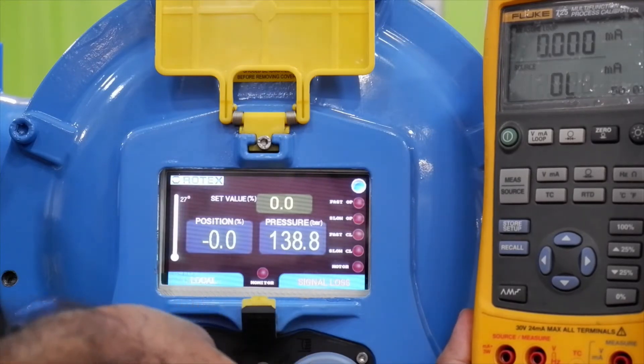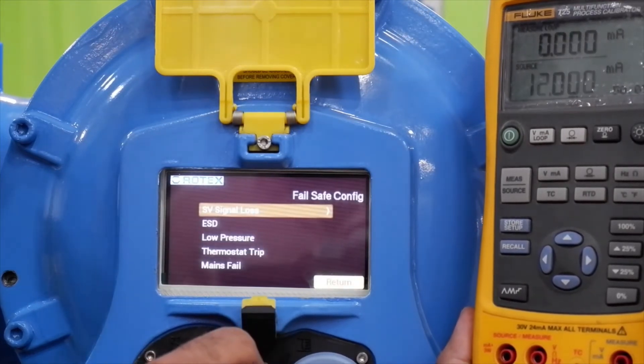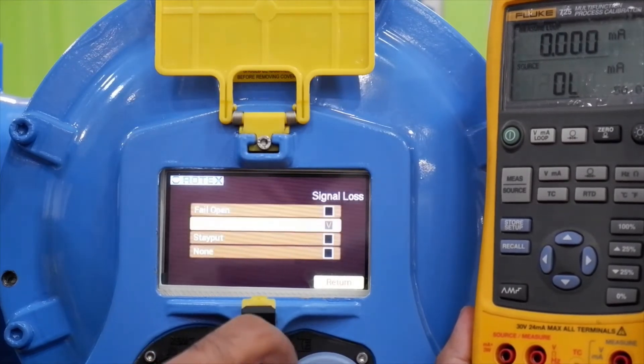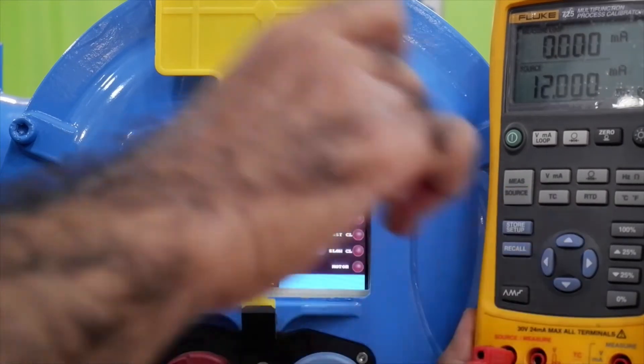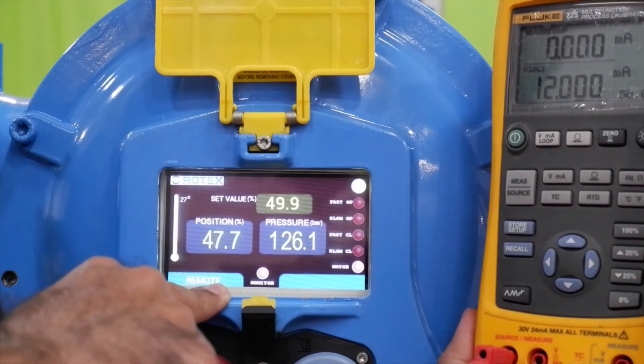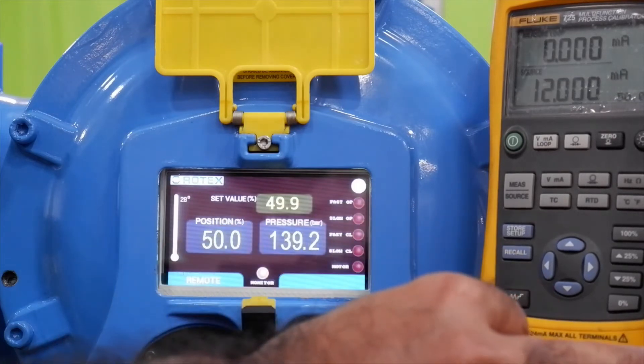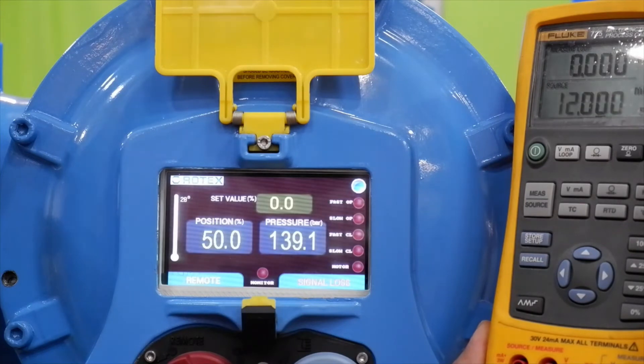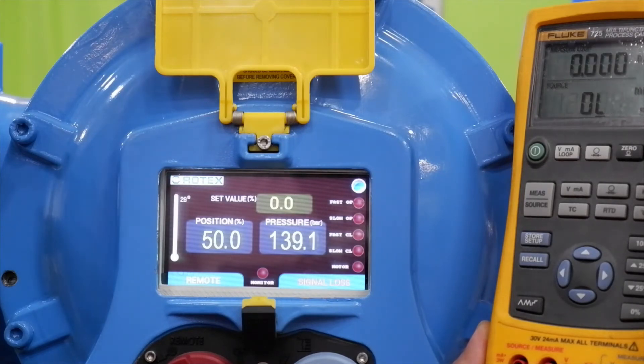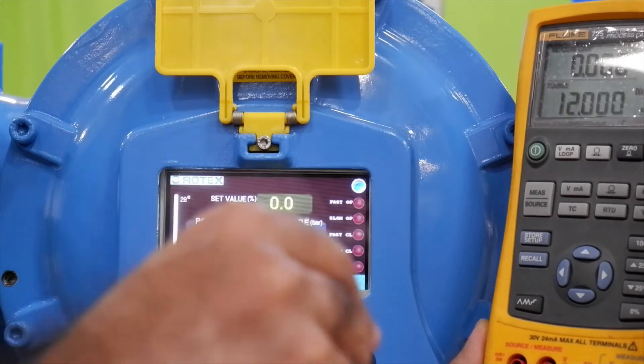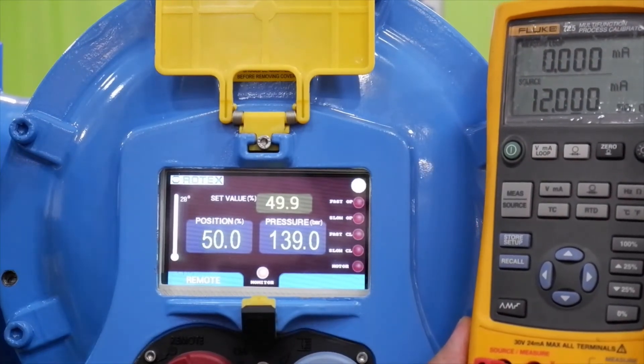If required, we can change the signal loss configuration by going into the fail safe configuration menu. We can change it to either fail open, fail close, or fail stay put. I have set it as stay put now. After receiving the signal, it is again coming back to 50 percent position. When I remove the signal, the valve stays at stay put at 50 percent, because signal loss fail safe configuration is set for stay put. Therefore, we have signal loss stay put and power fail stay put, or signal loss fail close as required by the customer.